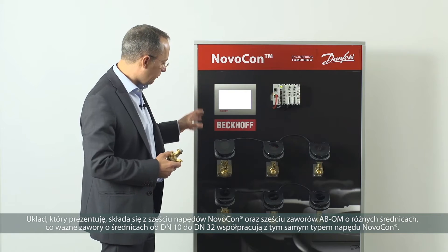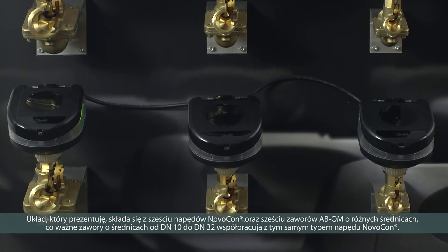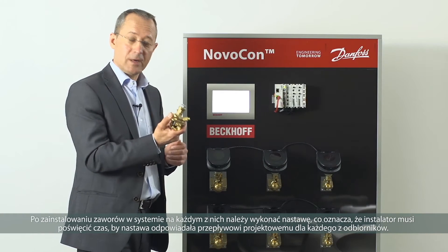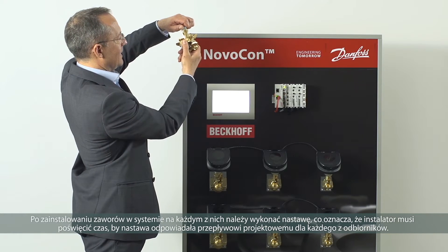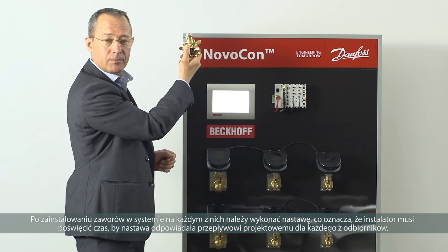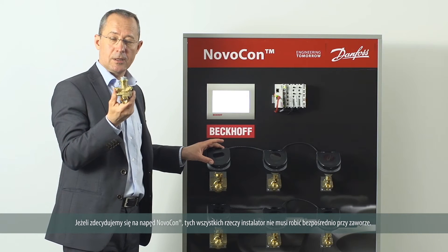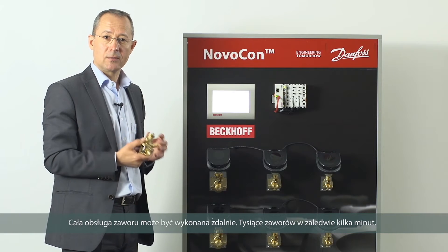The layout shown here shows six Novocons and six ABQMs of varying sizes — we go from DN10 to DN32 with a single actuator. After installation we need to commission the valve, which means the installer has to adjust the setting to the correct setting for the design flow of the terminal unit. It's difficult to see, difficult to reach, and time consuming. The Novocon means the installer doesn't need to do this — all valve settings can be done remotely, thousands of valves in just a few minutes.